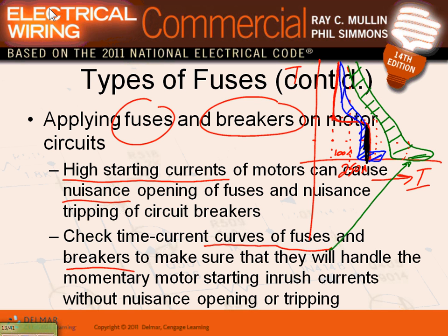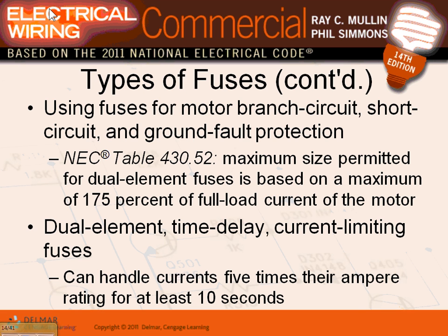Right in here, every time you start the motor, the circuit breaker will trip. Do you want that to happen in your project? No. That's why we do the overcurrent coordination. We use the rules in the code. When it says 2.5, you go up, unless you know otherwise, because every time they start the motor, it will trip. Okay.